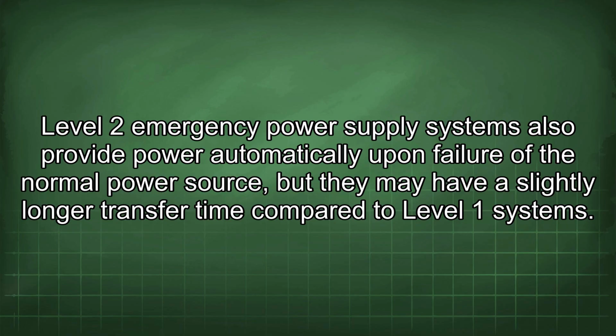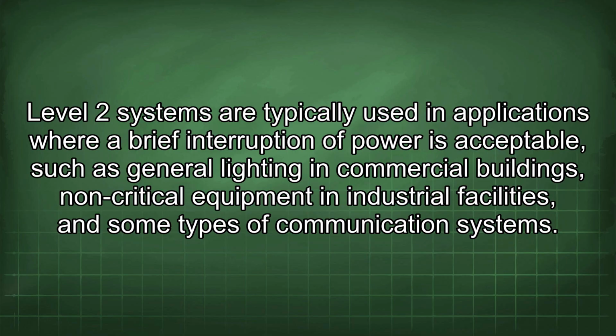Level 2 emergency power supply systems also provide power automatically upon failure of the normal power source, but they may have a slightly longer transfer time compared to Level 1 systems. Level 2 systems are typically used in applications where a brief interruption of power is acceptable, such as general lighting in commercial buildings, non-critical equipment in industrial facilities, and some types of communication systems.